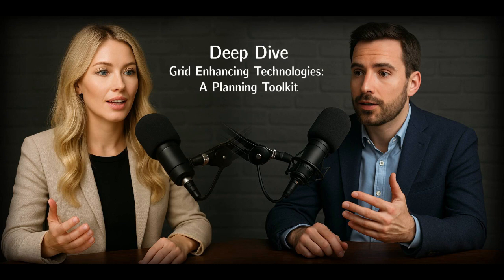What are some key FACTS devices engineers should be familiar with? Well, a common one is the static VAR compensator, SVC. SVC, what does that do? It's a shunt device, usually rated from 50 up to maybe 800 MVAR. The key things are speed and precision. It offers sub-cycle voltage regulation. Sub-cycle, that's fast. Very fast. And plus or minus 100% reactive power control. Very efficient too, over 98%.